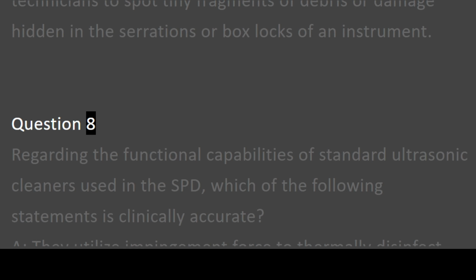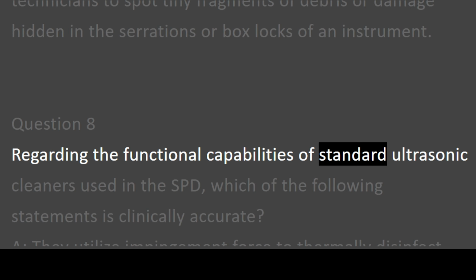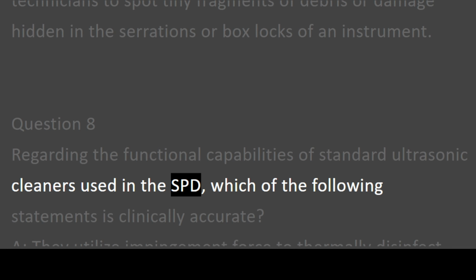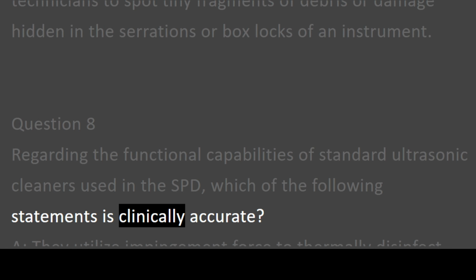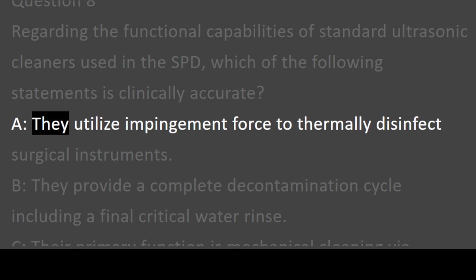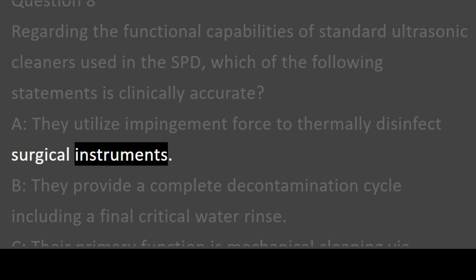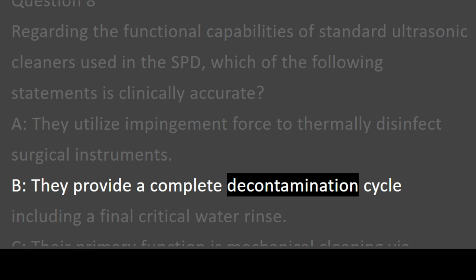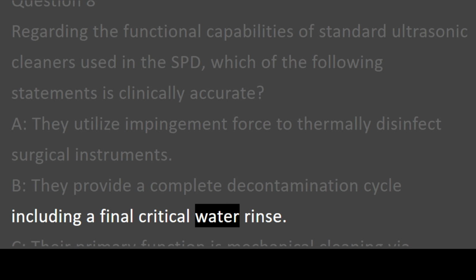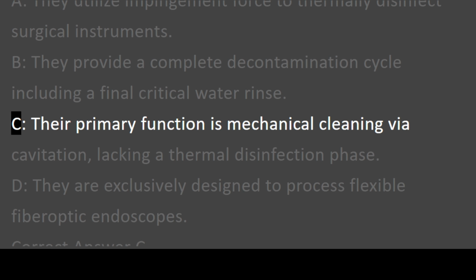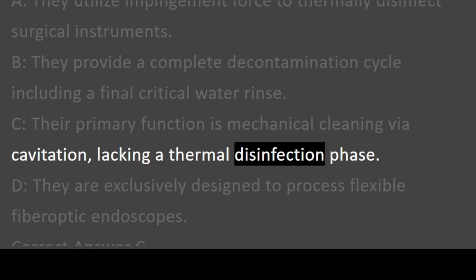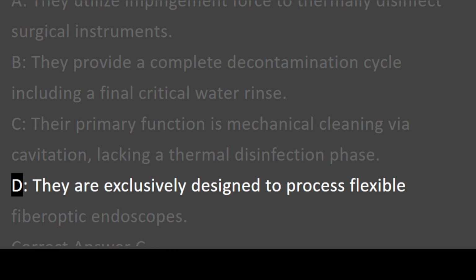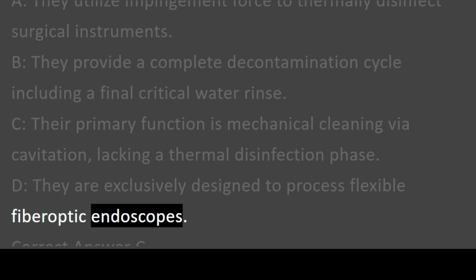Question 8. Regarding the functional capabilities of standard ultrasonic cleaners used in the SPD, which of the following statements is clinically accurate? A. They utilize impingement force to thermally disinfect surgical instruments. B. They provide a complete decontamination cycle including a final critical water rinse. C. Their primary function is mechanical cleaning via cavitation, lacking a thermal disinfection phase. D. They are exclusively designed to process flexible fiber optic endoscopes.